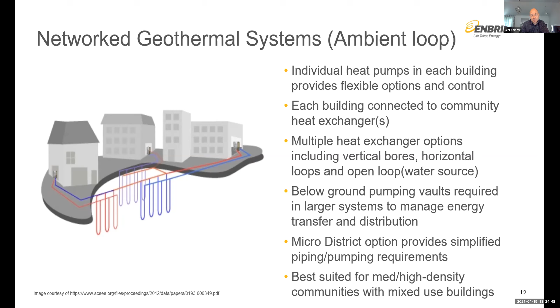There is the potential for one building, for example, if this building was a multi-unit residential and was cooling dominated, it would reject some of its heat energy into that loop field, which could then immediately bypass potentially the heat exchanger section and just go right to the next building and provide that waste heat as part of the heating source for the heating load in that additional building. So these are great systems. They are somewhat complex, depending on how they're laid out and the load diversity in the community. They often require below ground pumping vaults and a complex system of piping, but in certain applications where the energy sharing is available and those loads are diverse, they're a great opportunity to do an entire community with ground source heating systems.